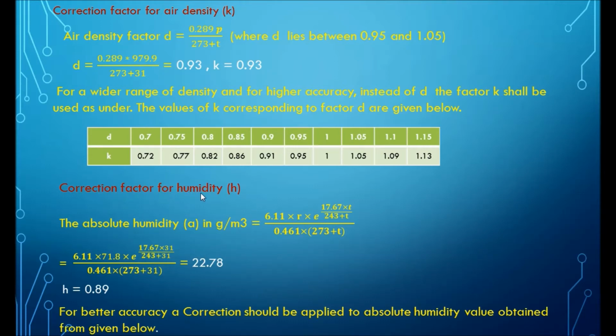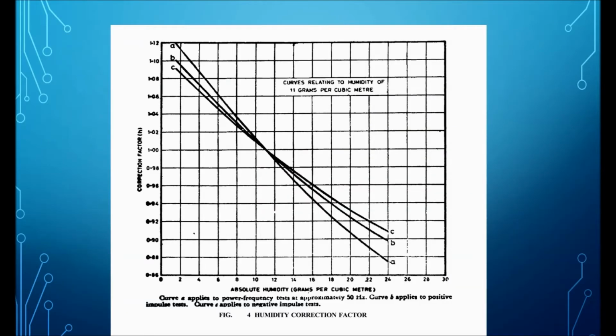Correction factor for humidity. This is the absolute humidity. First calculate the absolute humidity. Then, with the help of this graph, I have calculated the correction factor.